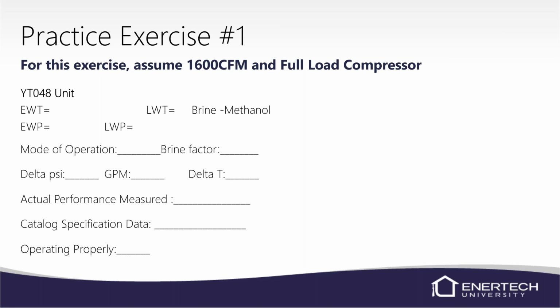So in this exercise, we're going to assume that we have 1600 CFM. The manuals will show CFM levels, so it doesn't really change. When we get to the manual, I'll explain it a little bit more, but it doesn't really change the BTUs a whole lot. So a lot of times I don't look at that unless my calculation is outside of my 10%, then I might go back and look at that kind of thing. A lot of times I don't really look at the CFMs right off the bat, because I don't open up the door to the lockout board to see what's flashing. I just start checking pressure drop, checking temperature, and going from there.